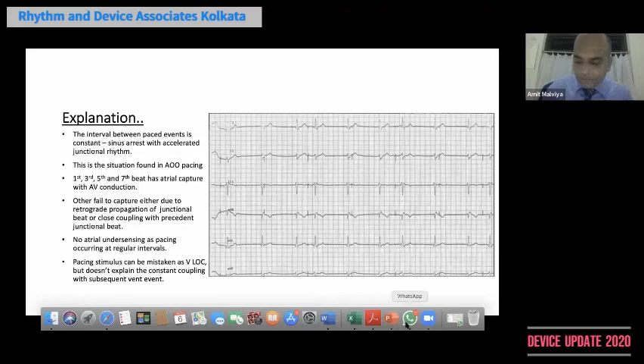So what is happening is some of the beats are captured and some are not captured due to retrograde propagation of junctional beat, or maybe a close coupling with preceding junctional beat. And this situation is commonly happening when the pacemaker is programmed to AOO mode. So the solution for this problem is to reprogram the pacemaker to DDI.